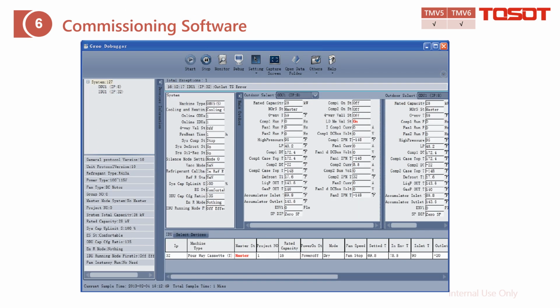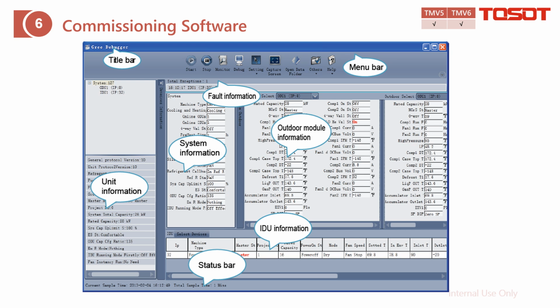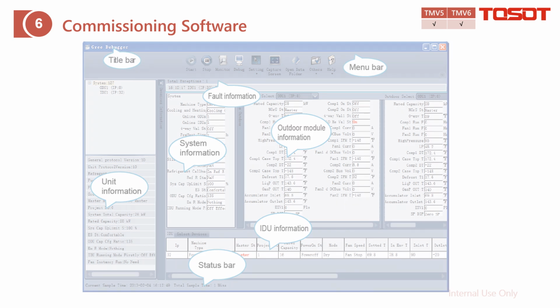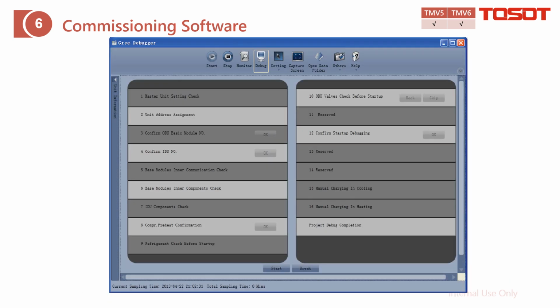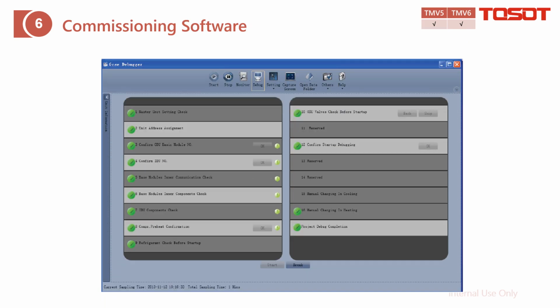After that, here you can check all the parameters, which will display directly to you. To check it out is really convenient and easy. Outdoor system information, outdoor unit information, indoor unit information, and also the error functions. And also you can do the commissioning from here. Also you can find that we display all the steps directly on the screen, and also the checking information. Also we display directly here. You can also have a check here and also confirm that the information from here is okay.